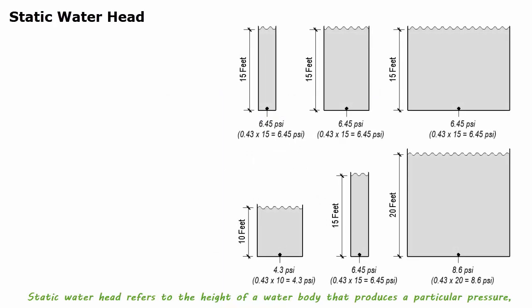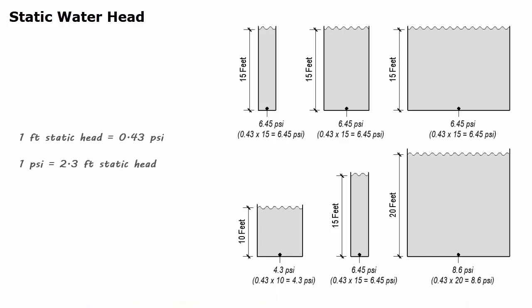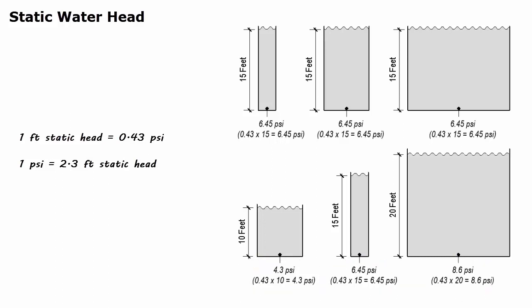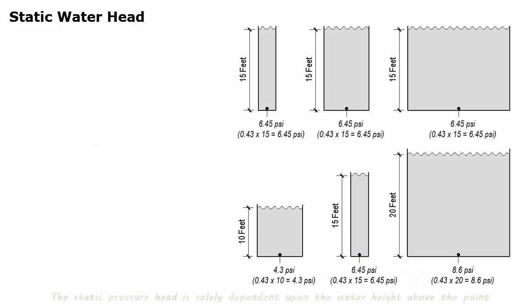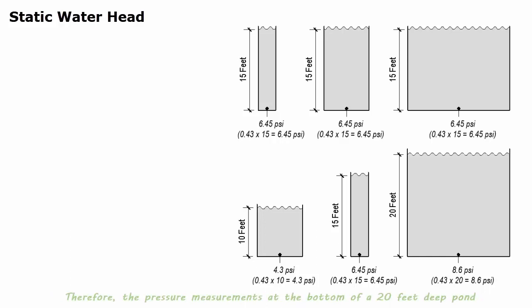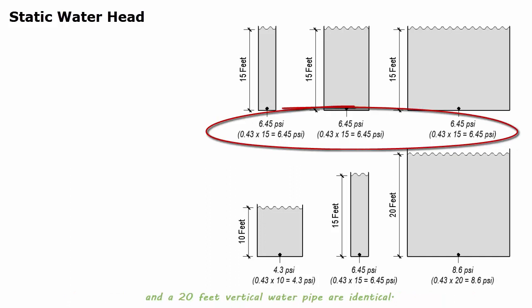Static water head refers to the height of a water body that produces a particular pressure, expressed in pounds per square inch (psi), at the bottom of that water body. 1 ft of static head is equal to 0.43 psi, or 1 psi is equal to 2.3 ft of static head. The static pressure head is solely dependent upon the water height above the point where the measurement is taken. Therefore, the pressure measurements at the bottom of a 20 ft deep pond and a 20 ft vertical water pipe are identical.